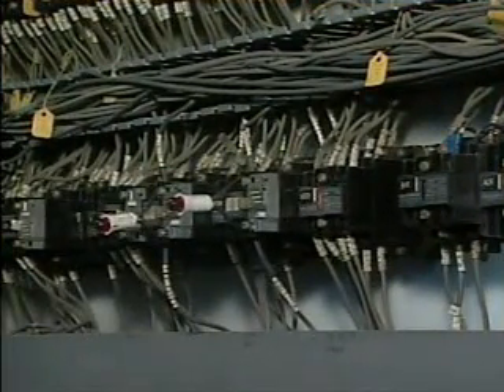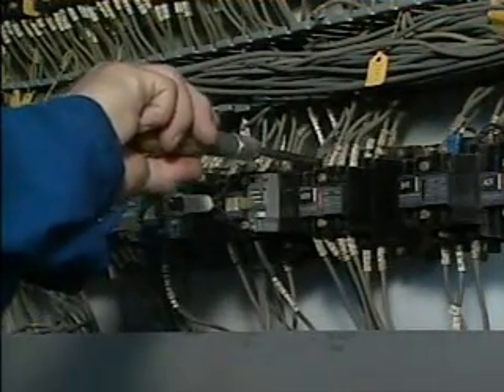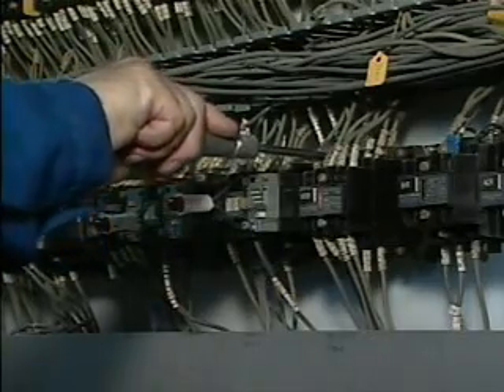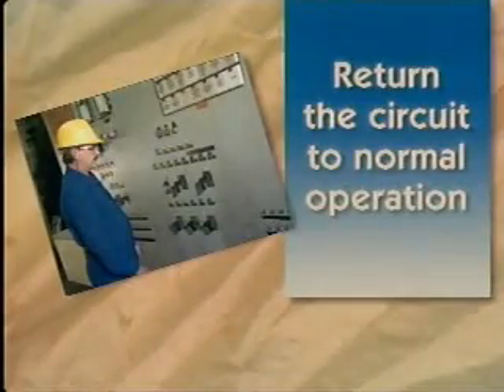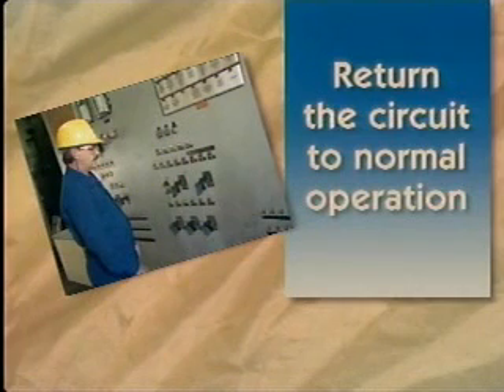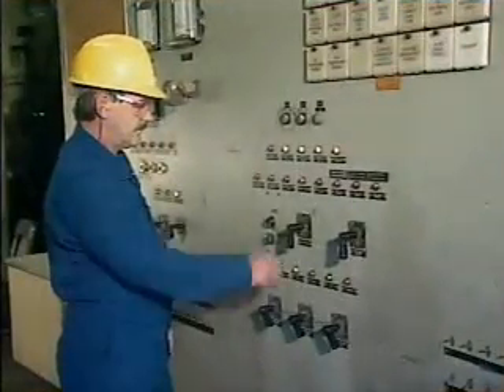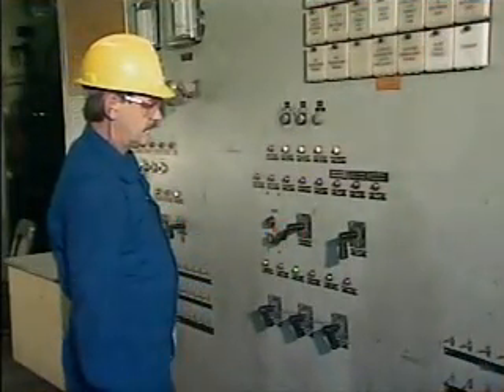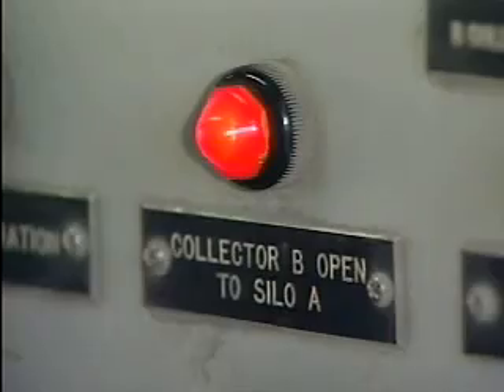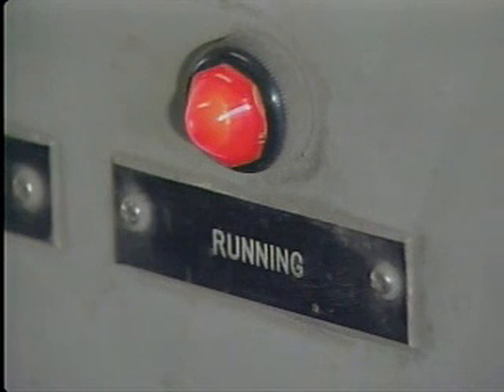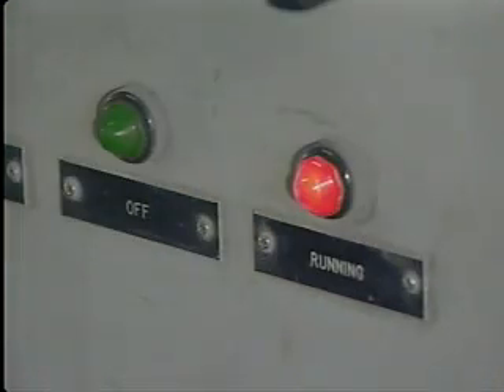After verifying that the relay and the wire are not energized, the electrician tightens the wire onto the relay. After he finishes, he returns to the control panel to attempt to return the circuit and the process to normal operation. The electrician attempts the startup procedure again. This time, after the silo crossover indicator light comes on, the vacuum pump and the pressure blower each turn on. The process is operating properly.